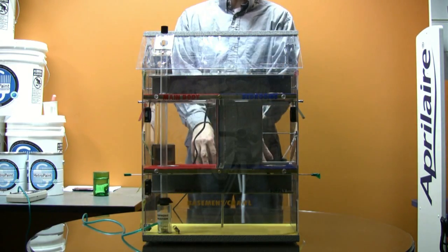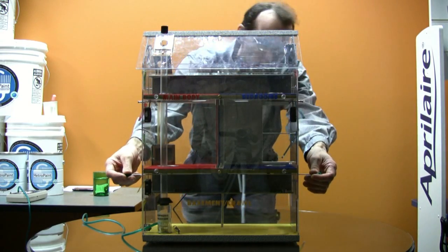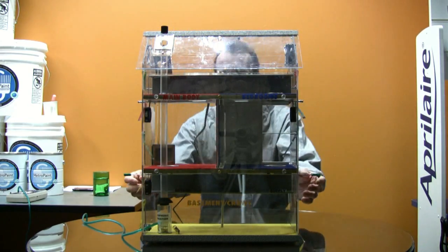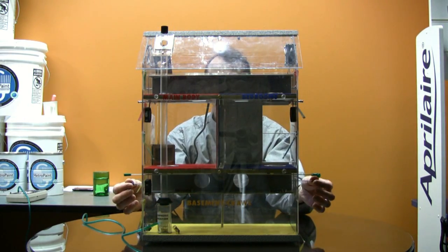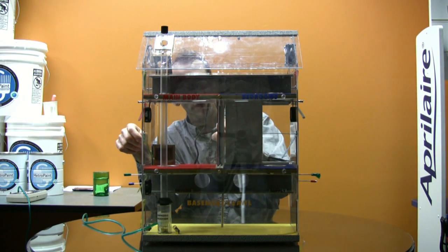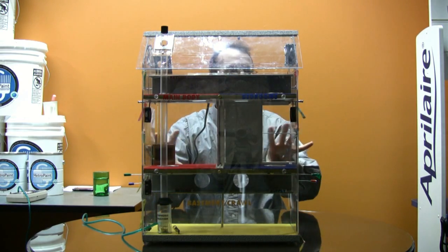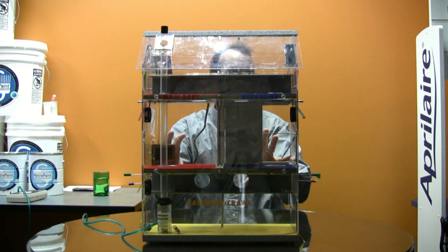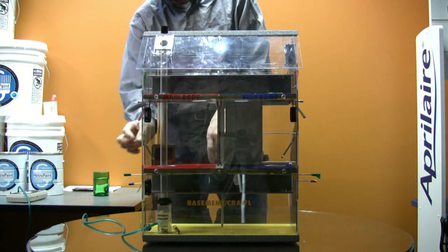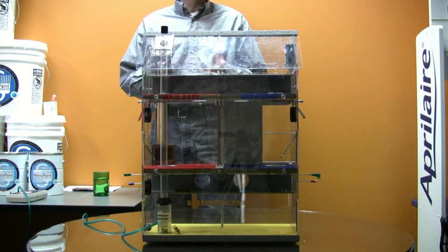don't necessarily have much conductivity into the basement from these other fans. So I can open these holes, making sure they're all the way open so that there is connection. I can also open some holes in the ductwork, which accentuates the connectivity around the house. I can open this door here. Now the house is all very open to itself, so we're getting a lot of airflow. The fans are able to pull all the way from down here, and now we've created a negative pressure of about 1.2 pascals.